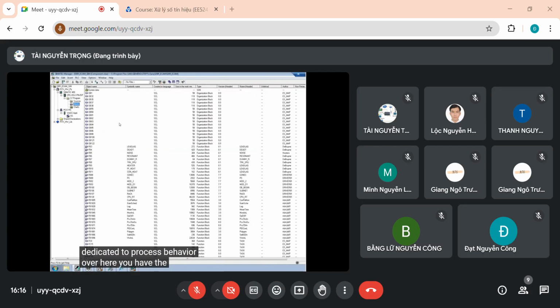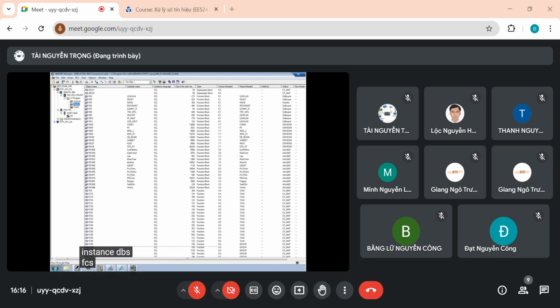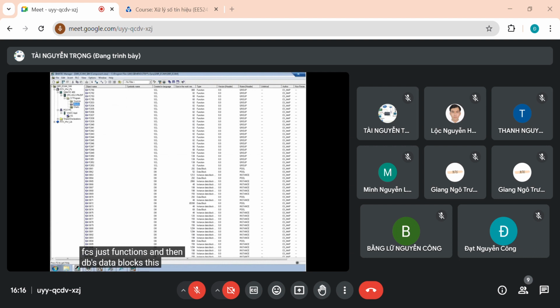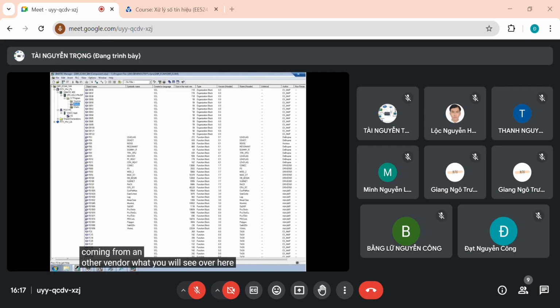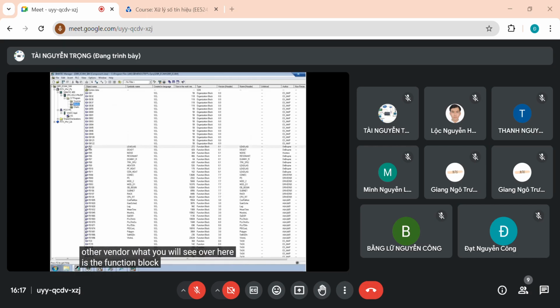Over here we have the block container with the FBs, so function blocks. We have instance DBs, FCs, just functions, and then DBs, data blocks. This looks very similar to what you've seen in other courses, but probably on a system coming from another vendor. What you will see over here is the function block lead lag that will implement the lead lag system, and it has resulted from the compilation of the code that I just showed you before.